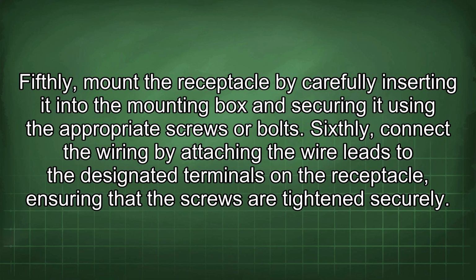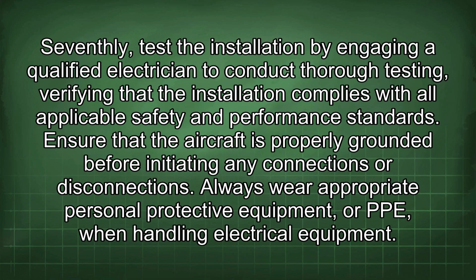Fifthly, mount the receptacle by carefully inserting it into the mounting box and securing it using the appropriate screws or bolts. Sixthly, connect the wiring by attaching the wire leads to the designated terminals on the receptacle, ensuring that the screws are tightened securely. Seventhly, test the installation by engaging a qualified electrician to conduct thorough testing, verifying that the installation complies with all applicable safety and performance standards. Ensure that the aircraft is properly grounded before initiating any connections or disconnections. Always wear appropriate personal protective equipment, or PPE, when handling electrical equipment.